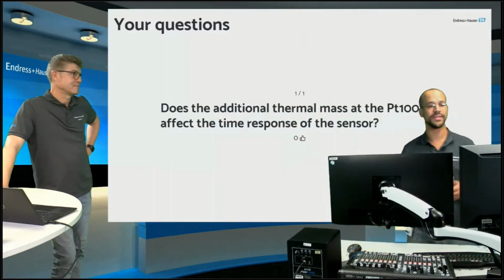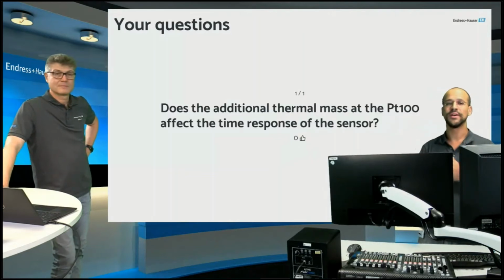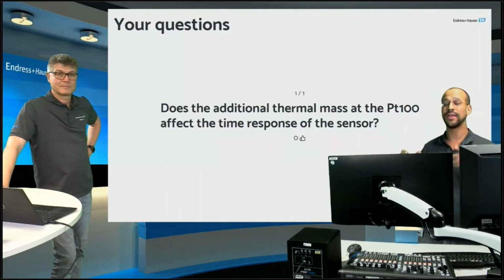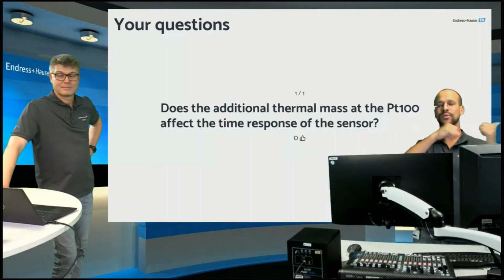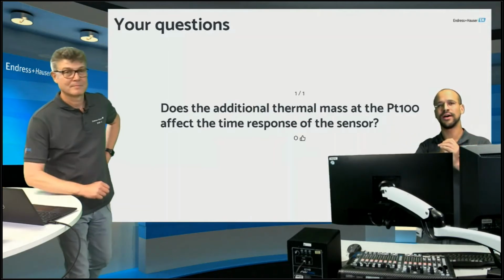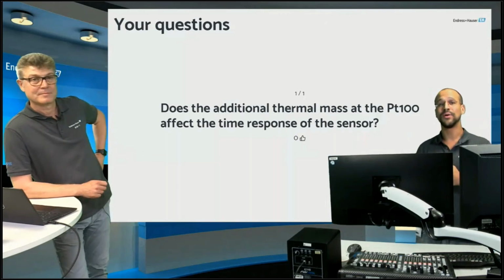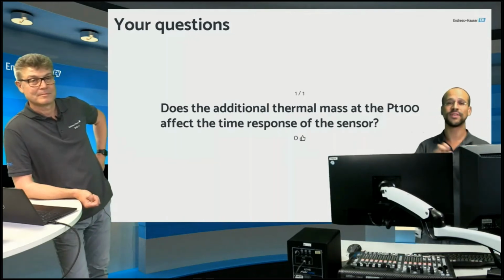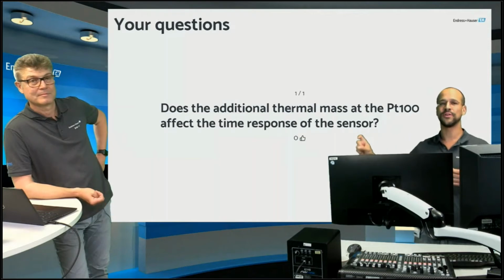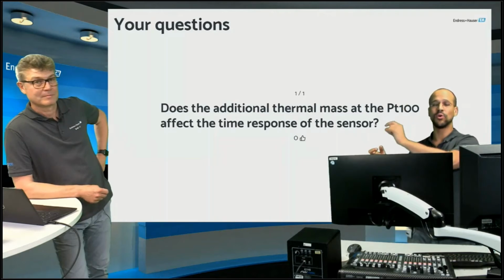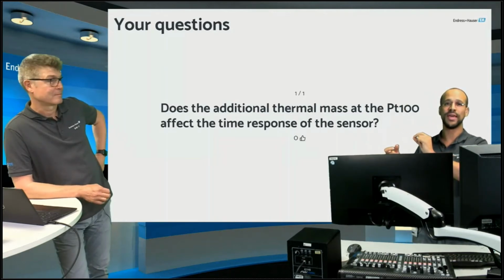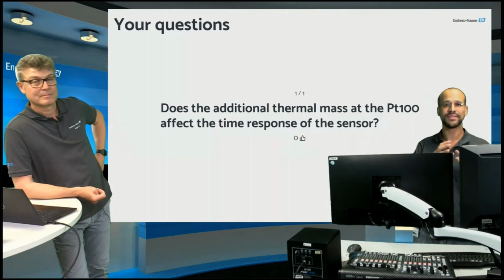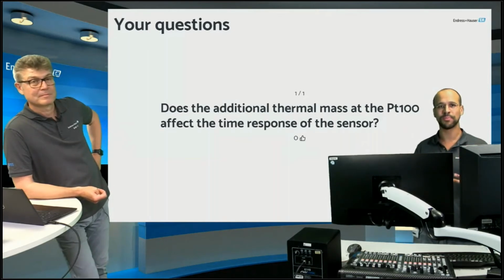The question is whether this additional thermal mass, the reference, could create a different response time in the sensor. If you were not there last Tuesday, where we had an online seminar on sensor technologies in general and what is important about the response time of a sensor, it is always the position of the sensor. Our iTherm QuickSense is so fast because it is soldered right to the tip of the measuring insert.